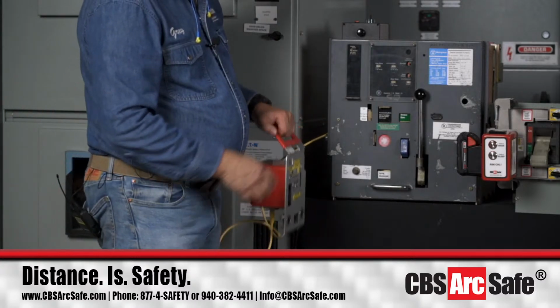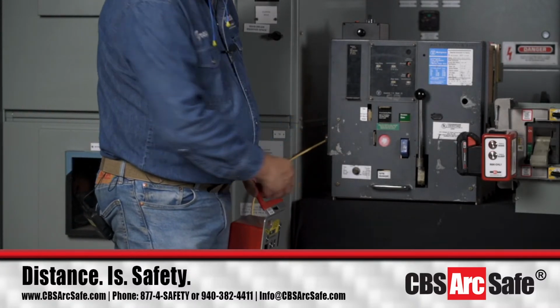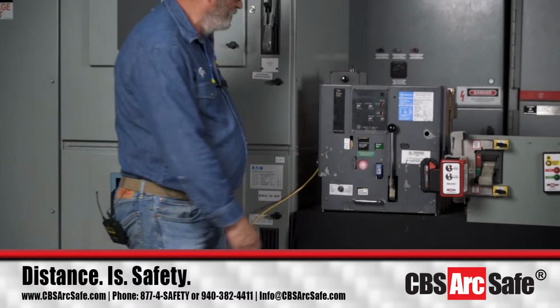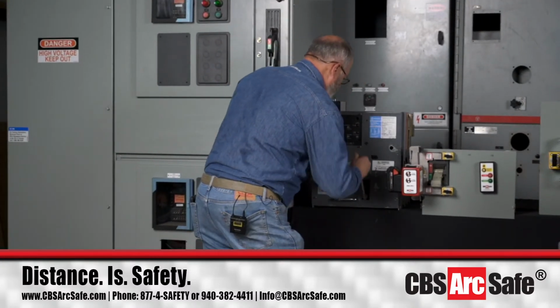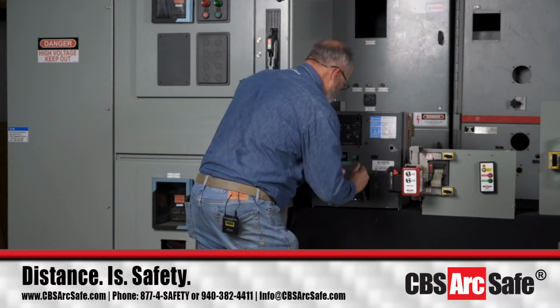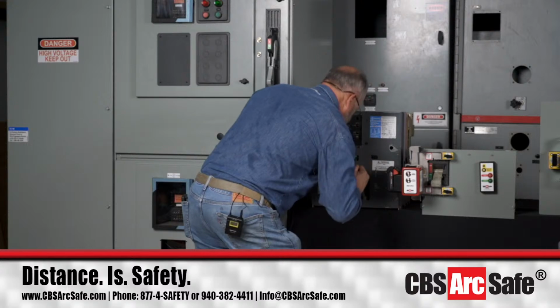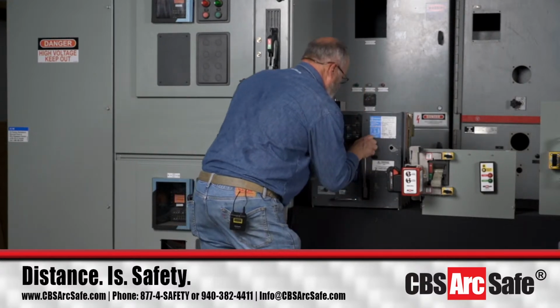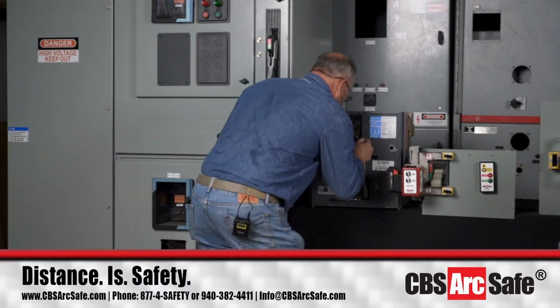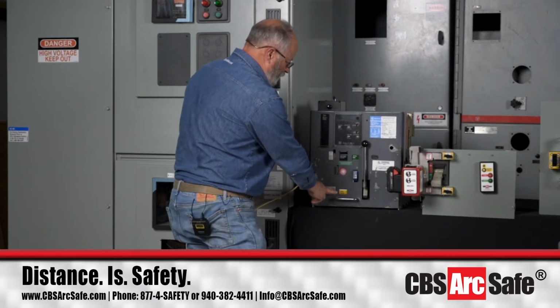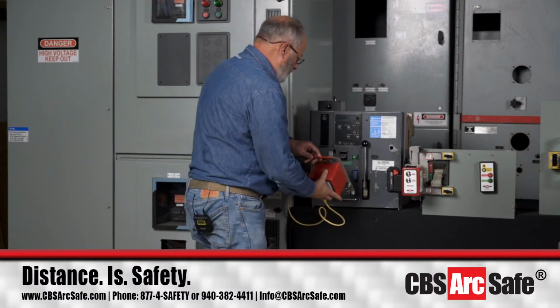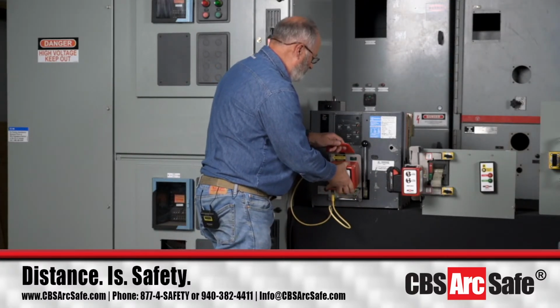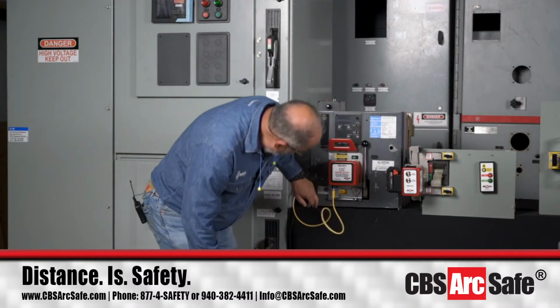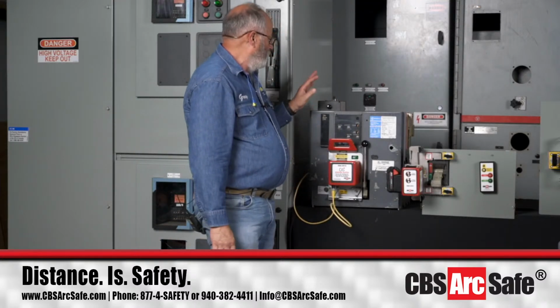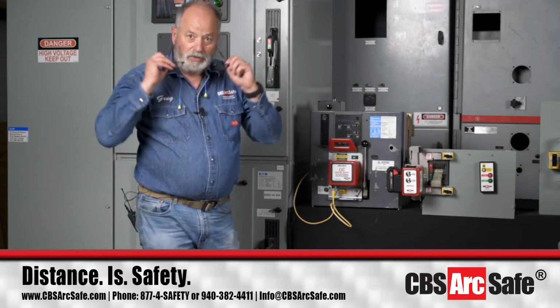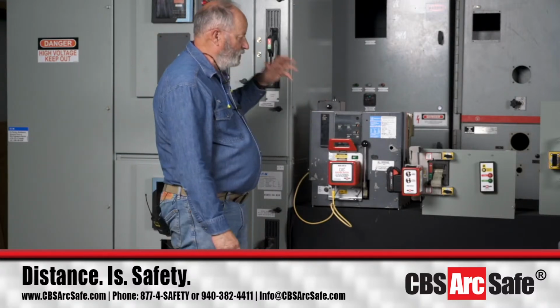Now, this is only going to close and trip the breaker. I still have to charge the spring manually, and I'm going to do that operation first. Okay, now we can see we've got a charged spring. One thing to remember about all this is we can see that it's open, and we've got a charged spring here.